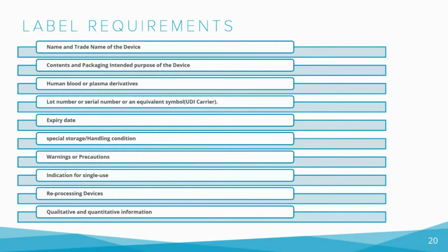Next, label requirements. Chapter 23.2 of the MDR outlines the general requirements for labeling of medical devices. The first requirement is the name and registered trade name or registered trademark of the manufacturer and the address of its registered place of business. Through this, the label shall be updated with the legal manufacturer's name and address. If the legal manufacturer is from outside of the European Union, then the authorized representative or importer or exporter or both also need to be included along with the legal manufacturer.